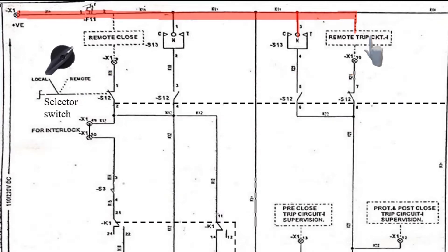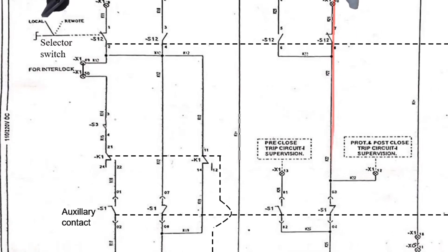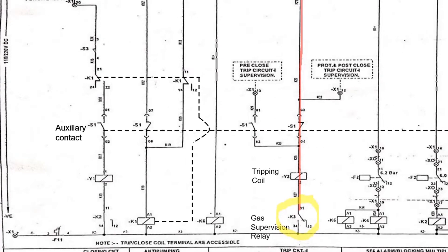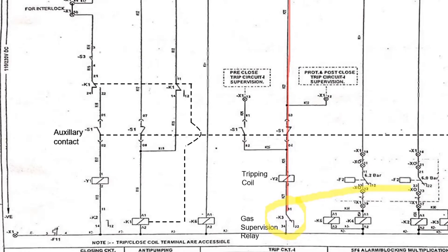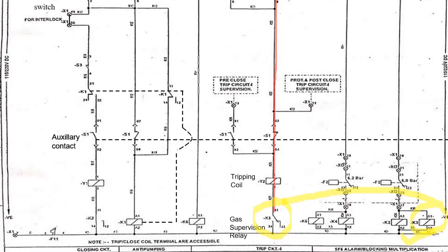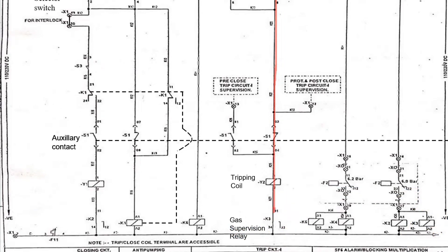Now when the operator present in the control room performs the trip operation, the current will flow like this, passing through the tripping coil and will stop at the gas supervision relay. Here K3 relay will close its contact only when the SF6 gas pressure in the circuit breaker is more than 6 bar. When it is more than 6 bar, the relay gets energized and changes its contact from NO to closed position. Then the current, by flowing through K3 and fuse, completes the tripping circuit.